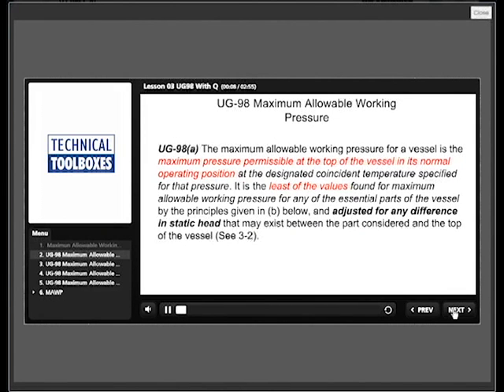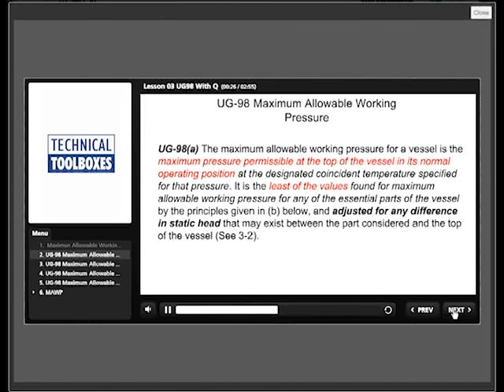The maximum allowable working pressure for a vessel is the maximum pressure permissible at the top of the vessel in its normal operating position at the designated coincident temperature specified for that pressure. It is the least of the values found for maximum allowable working pressure for any of the essential parts of the vessel, adjusted for any difference in static head that may exist between the part considered and the top of the vessel. This seems like a simple statement, but there's more to it than meets the eye.